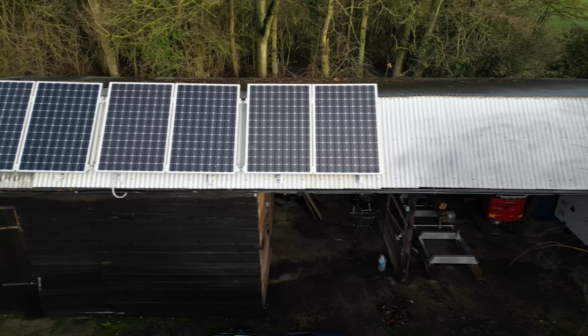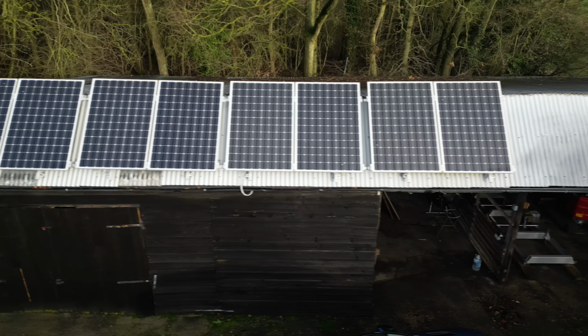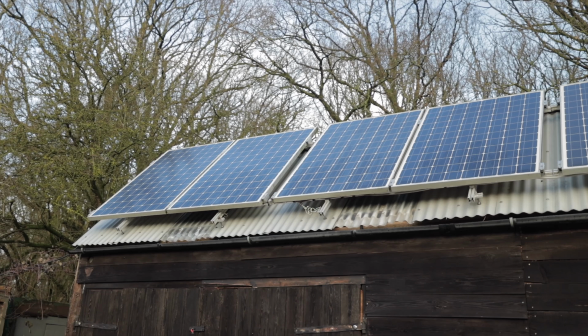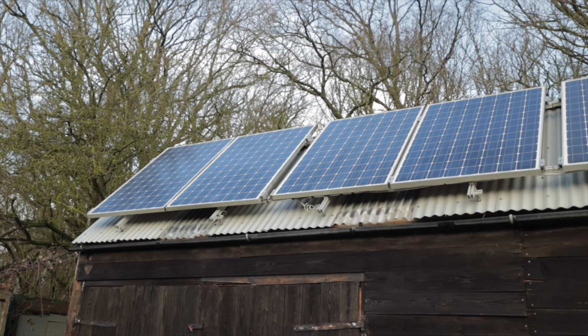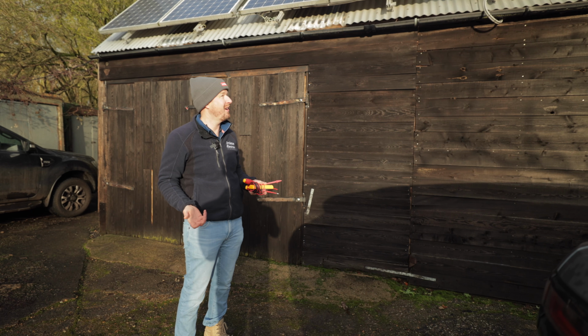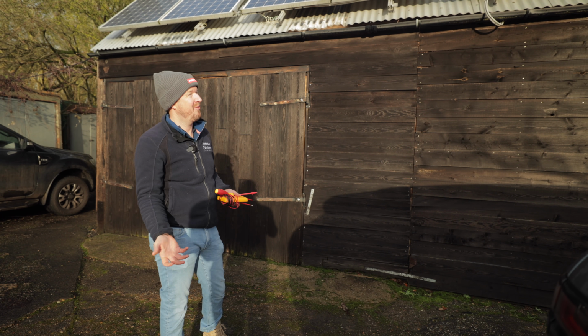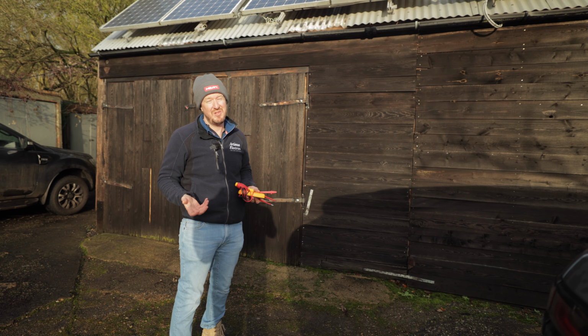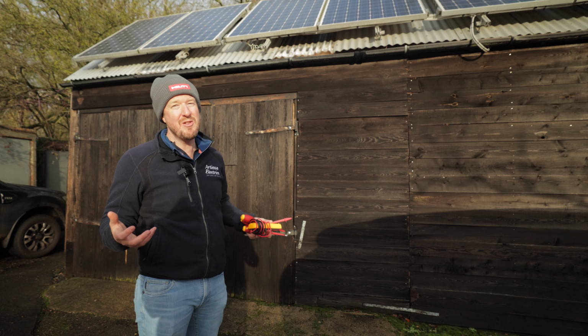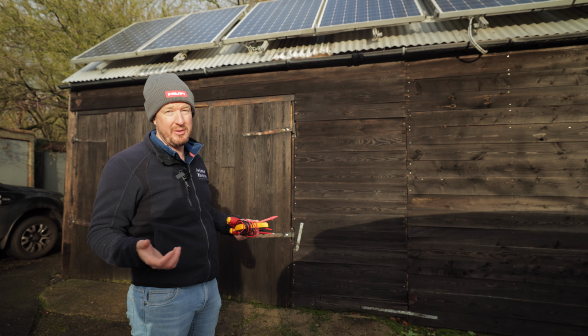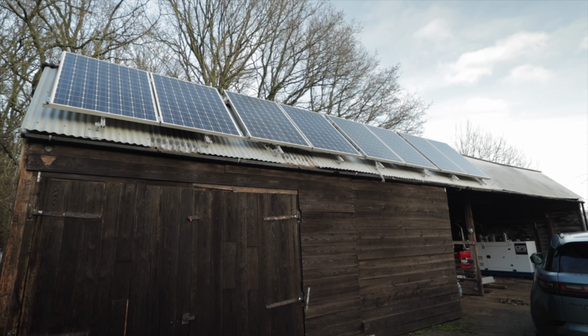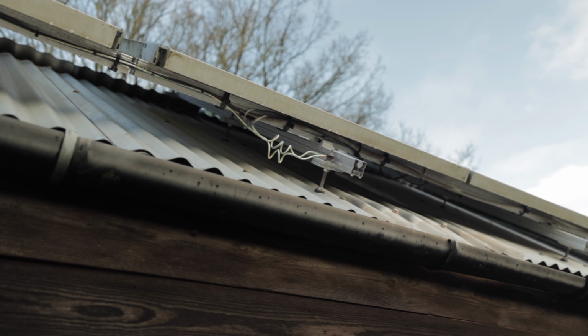There are 8 panels here on this south-facing roof of this outbuilding. They're pretty old - the customer reckons about 10 years old, about 225 watts each. So this array in itself is only about 2,000 watts, which is obviously not enough to power a modern home. Looking at the condition of the array and the way it's been wired up, there's already a few alarm bells ringing.